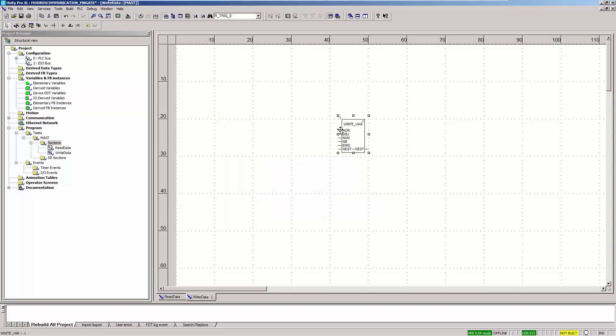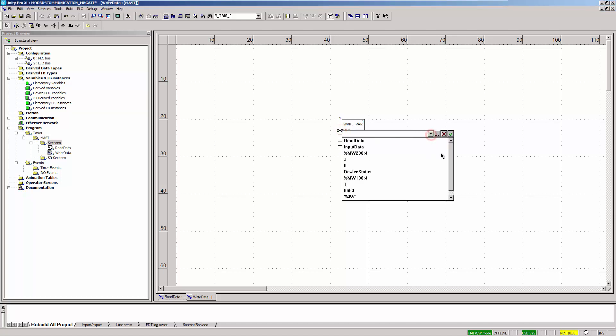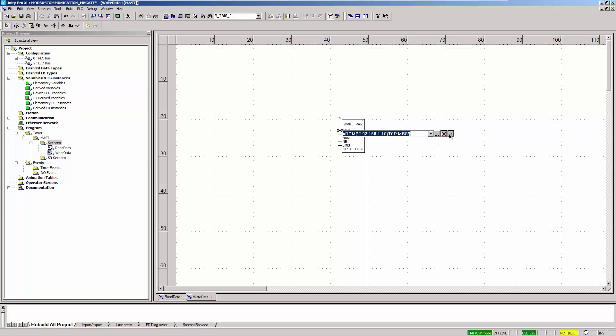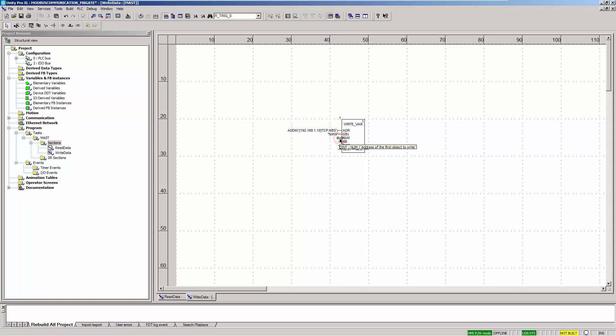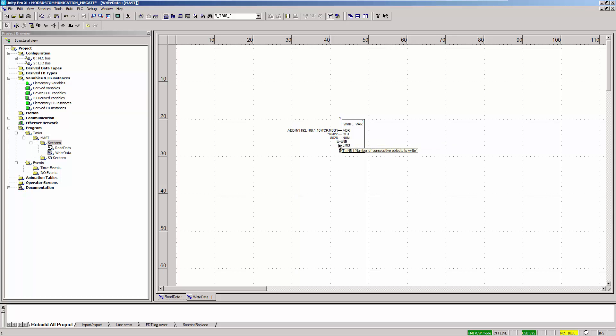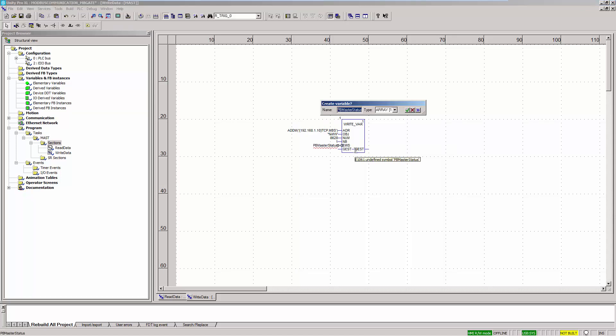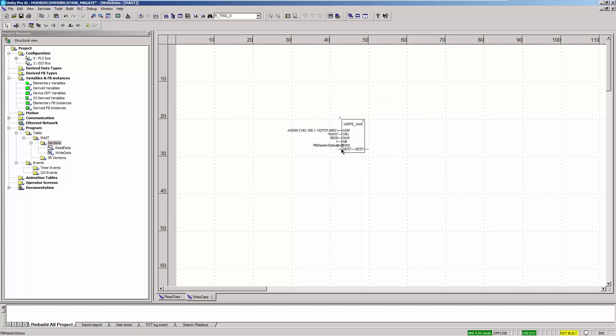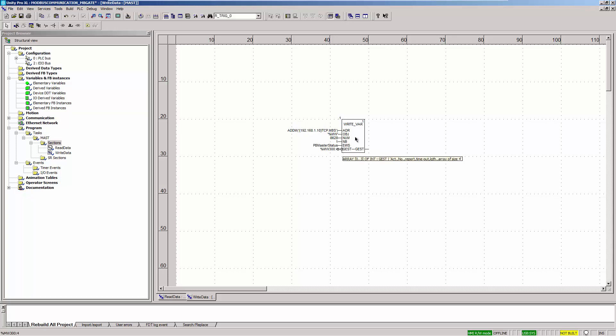The address already defined for the READ_VAR function can be selected as the address. In the object type field, %MW has to be entered for the holding register according to the IEC standard. The status for the Profibus Master of segment PA1 is mapped to holding register 8628. The number of registers is 1. Create an array variable in the EMIS parameter — this is used to describe the data to be written. The length of the array must be adjusted accordingly.